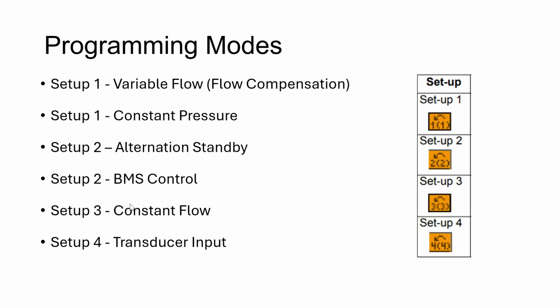That's correct. Yes, if it's an external signal, it ignores all the software for self-sensing functions, and it just looks at the input signal from a 0 to 10 volt or a 4 to 20 milliamp signal. And then replacement drive, we do have replacement drives. Oh, excuse me, we don't have them, but we can get them.